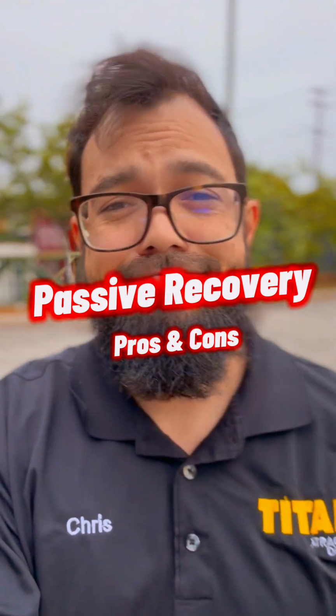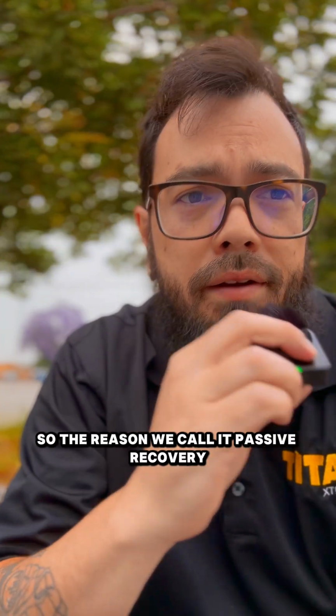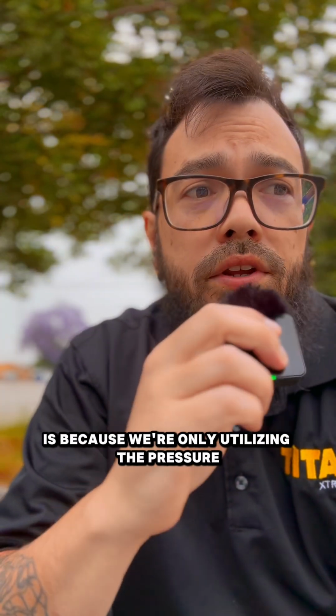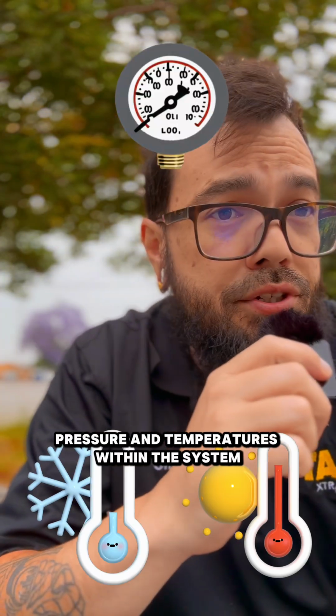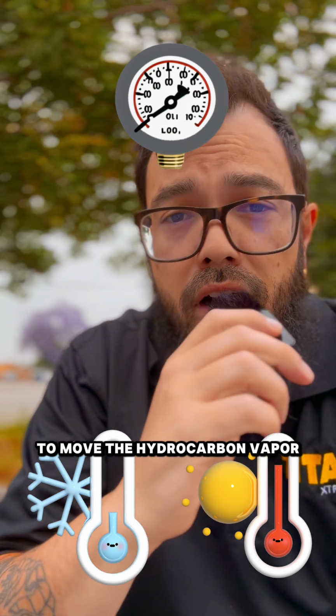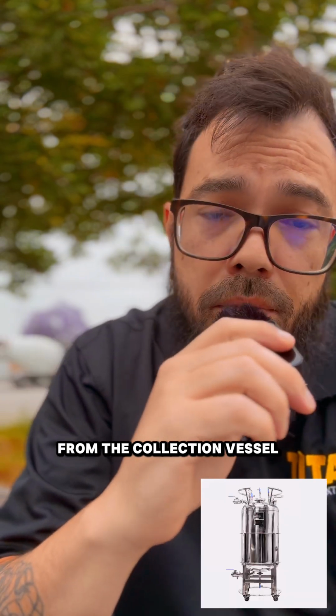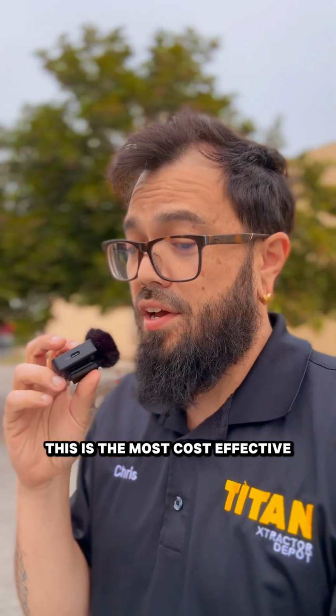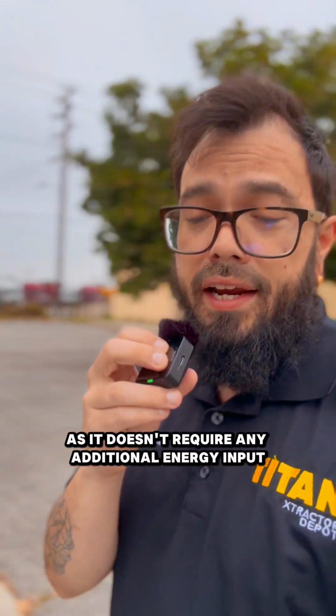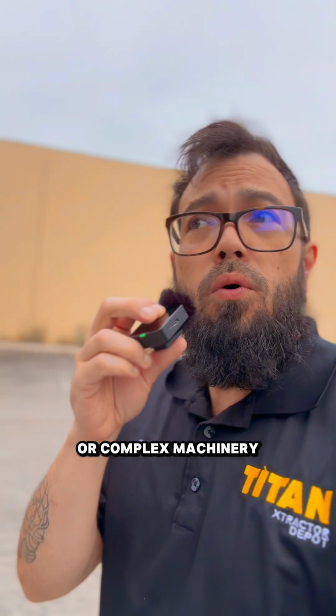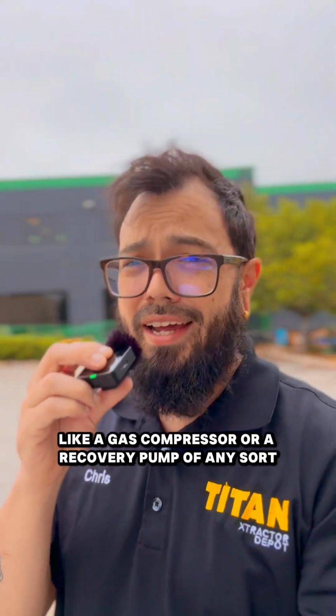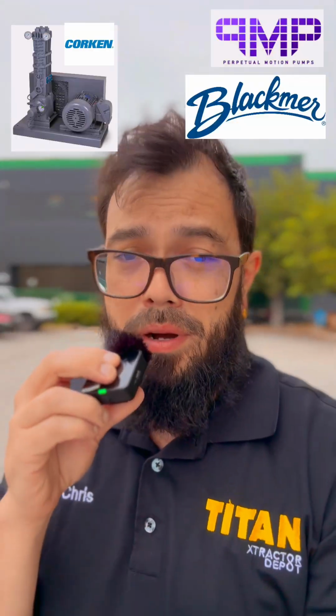Let's get it. The reason we call it passive recovery is because we're only utilizing the pressures and temperatures within the system to move the hydrocarbon vapor from the collection vessel back to the solvent tank. It is the most cost-effective and straightforward method as it doesn't require any additional energy input or complex machinery like a gas compressor or recovery pump of any sort.